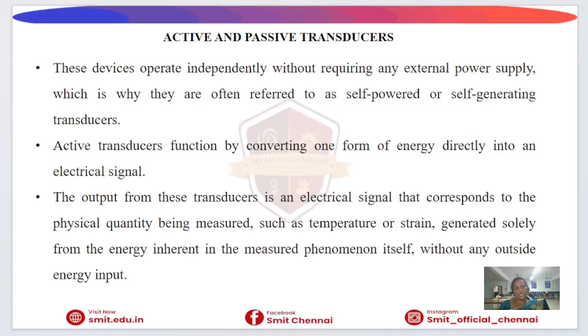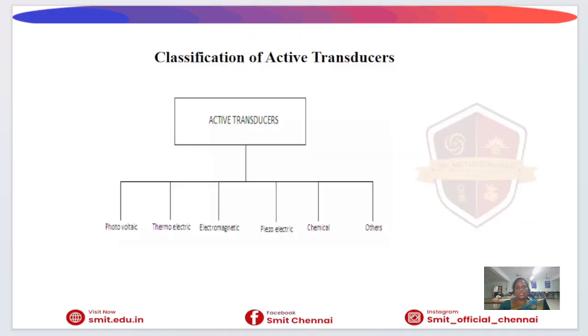One of the most important classifications is active and passive transducers. Active transducers generate their own electrical output without requiring an external power source. They convert the energy of the measured quantity directly into electrical energy. Passive transducers, on the other hand, require an external power supply. They do not generate electrical signals by themselves but produce changes in electrical parameters such as resistance, capacitance, or inductance. This distinction is important when selecting transducers for specific applications.